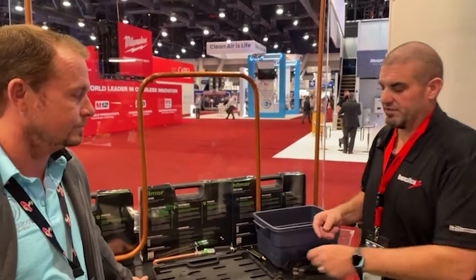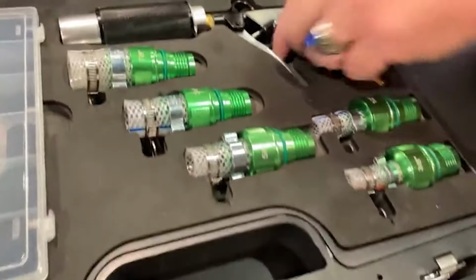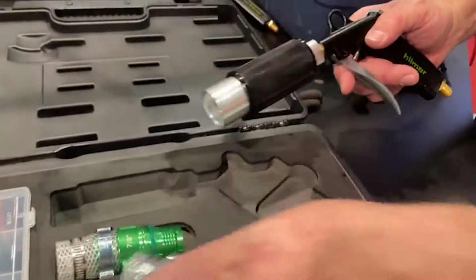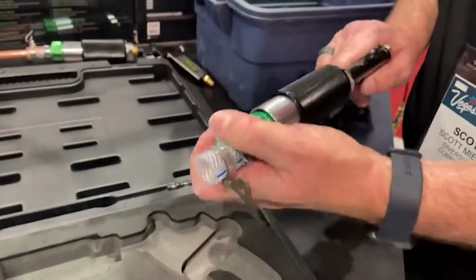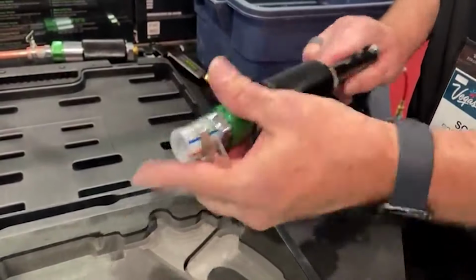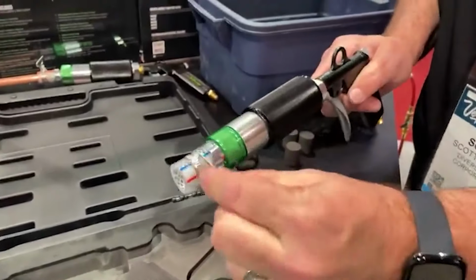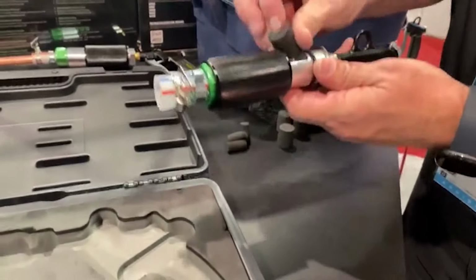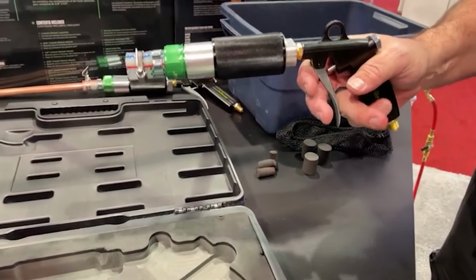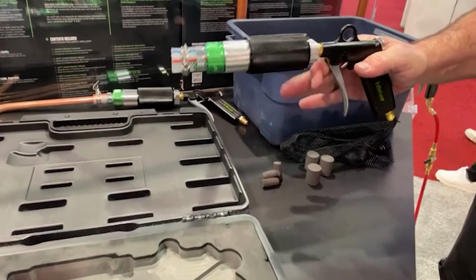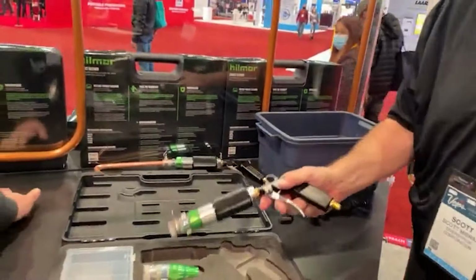Yep. So how you hook this up is you grab the launching tool, you pick the appropriate nozzle. We're going to go to 3/4 here real quick. You screw the nozzle onto the gun itself. You attach it to your line set via the thumb screw, and you open the chamber, put your pig in the chamber, close the chamber, hook it up to your 70 PSI compressed nitrogen tank, pull and hold the trigger till that pig starts to fly.